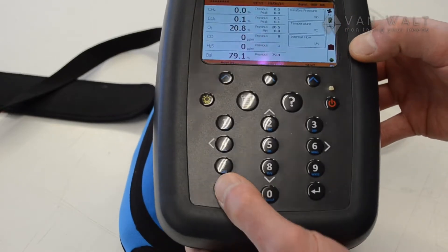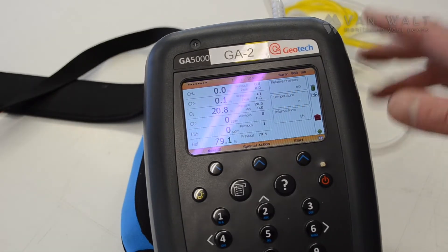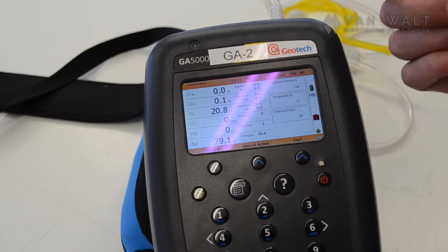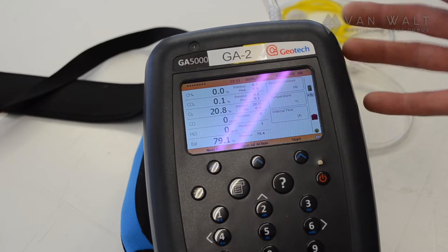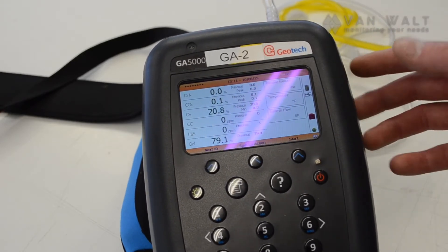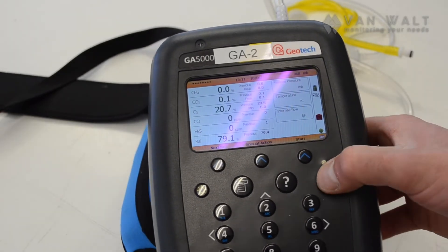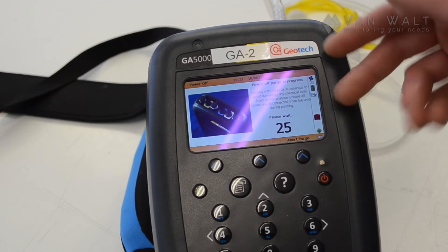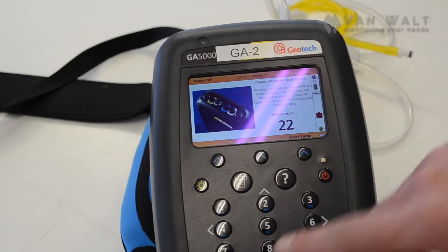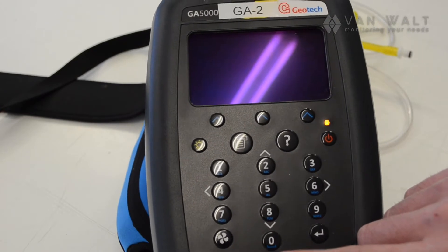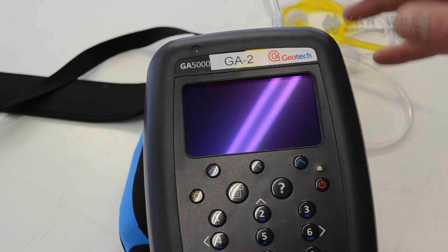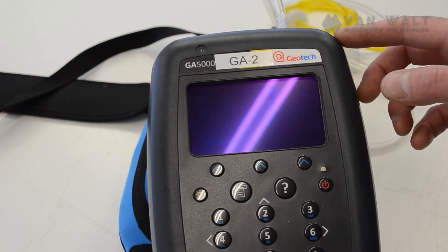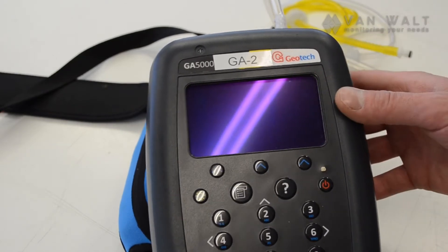I'm turning the pump back off — that's really simple. For the analysis, pressure, and flow testing you press the start button, but for a simple gas measurement that's all you need to do. When you're done, click and hold the power button and it will switch off. It purges first. We had a clear sample with no contaminants, so I can turn the pump off immediately. If you have had high contaminant readings, let the machine purge itself to clear the sensors before it turns off.